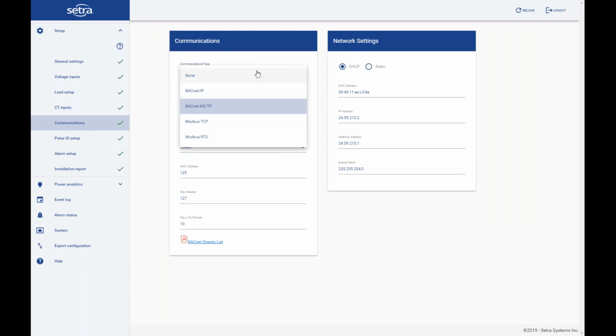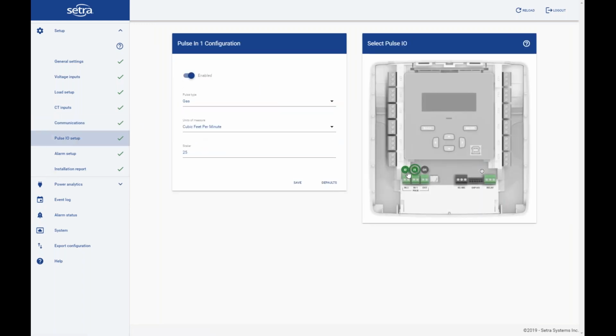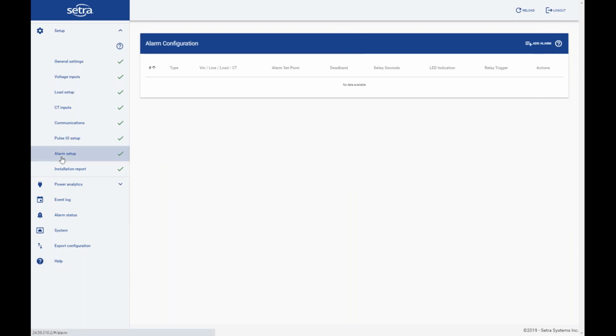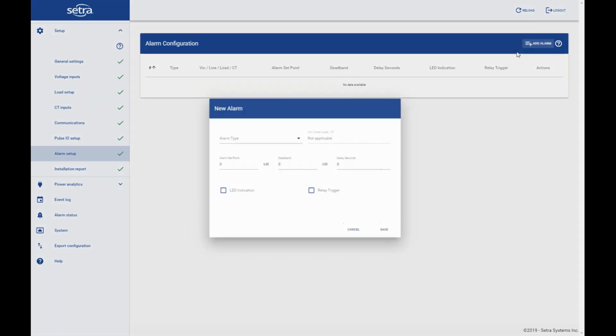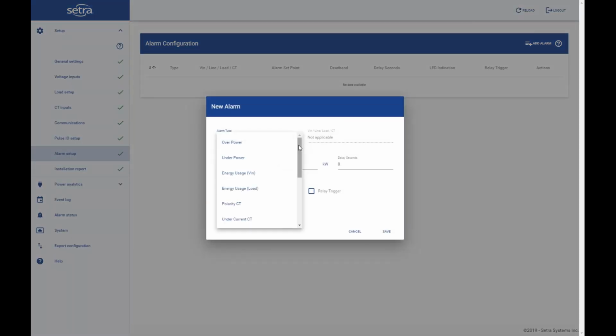Communications, this is where you'll set your BACnet or Modbus parameters, as well as your network settings. Pulse inputs, so you can see there are 2 pulse inputs, and then we have 1 pulse output. You can configure those for whatever meter's coming into the unit, as well as any accumulating value. We have quite a bit of alarming that you can put on your meter. So you can add an alarm, and there are many different alarms that you can set. These alarms will act locally on the meter. You'll be able to see them through the web portal. And if you're using BACnet, you'll see them as event notifications. With Modbus, there's not really an alarming part of that protocol, but with BACnet, you'll be able to see those over the BACnet network.